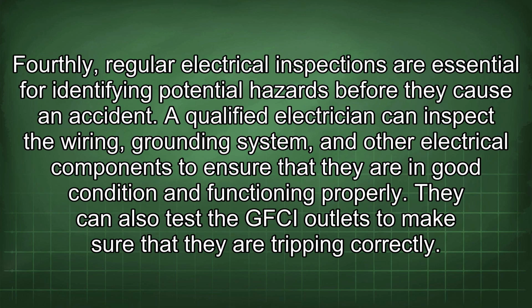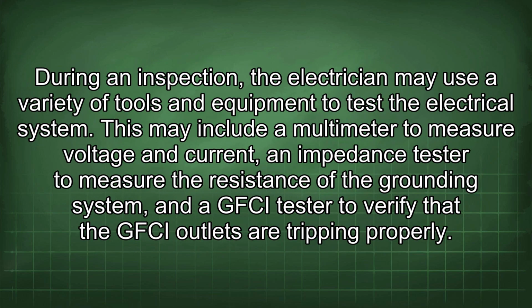Fourthly, regular electrical inspections are essential for identifying potential hazards before they cause an accident. A qualified electrician can inspect the wiring, grounding system, and other electrical components to ensure that they are in good condition and functioning properly. They can also test the GFCI outlets to make sure that they are tripping correctly. During inspection, the electrician may use a variety of tools and equipment to test the electrical system. This may include a multimeter to measure voltage and current, an impedance tester to measure the resistance of the grounding system, and a GFCI tester to verify that the GFCI outlets are tripping properly.